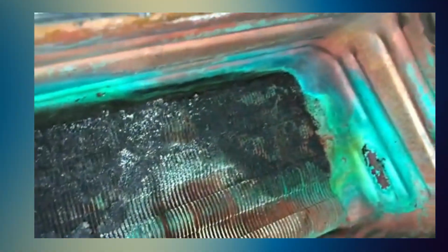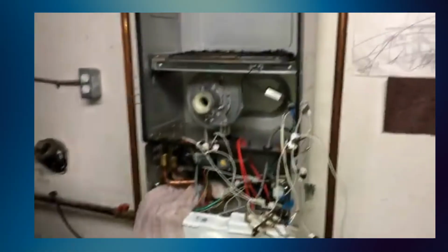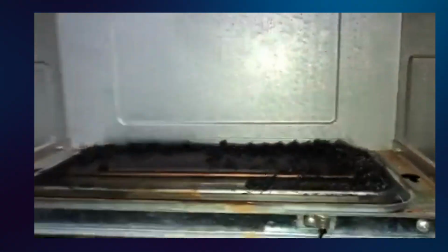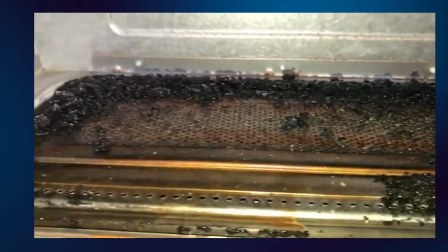The third cause is air in the gas line. This can happen after gas supply work, after the boiler has been off for a long time, or after replacing gas components. The boiler may attempt ignition, but fail because the mixture is not right yet. Sometimes a proper reset clears it, but if the fault persists, it needs service diagnosis.